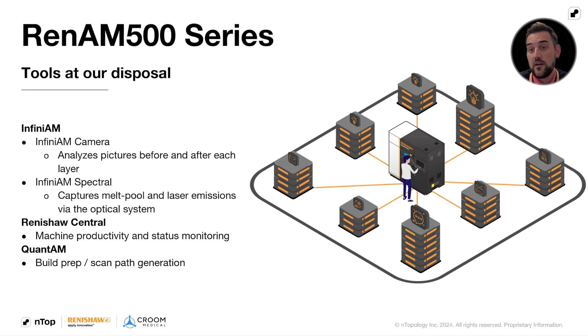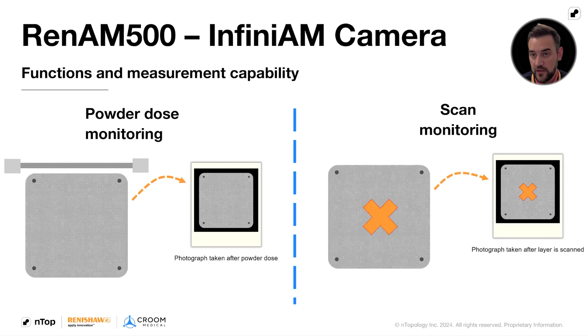So the camera, just to go through this quickly: there's a white light photography camera within the build chamber that'll take a picture of the layer after a dose has been completed and a picture of the layer after a scan pass has been completed, so after the laser is done welding. Over time, across a 2000 layer build, if you will, we can end up stacking those images and turning them into a grayscale and identify a mean RMS, root mean squared distribution of gray, across each of those profile sets. So while this isn't necessarily quantitative data, it allows the end user to identify quantitative or qualitative metrics, excuse me, to identify if there's any deviation within the build sequence, right?